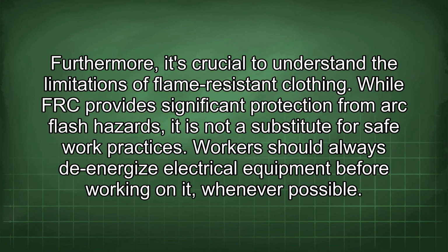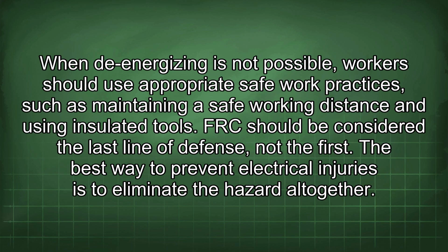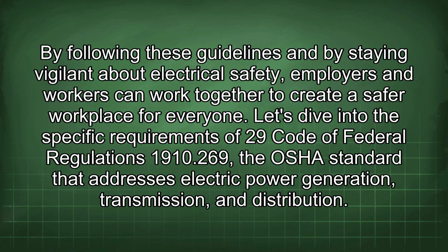Furthermore, it's crucial to understand the limitations of flame-resistant clothing. While FRC provides significant protection from arc flash hazards, it is not a substitute for safe work practices. Workers should always de-energize electrical equipment before working on it, whenever possible. When de-energizing is not possible, workers should use appropriate safe work practices such as maintaining a safe working distance and using insulated tools. FRC should be considered the last line of defense, not the first. The best way to prevent electrical injuries is to eliminate the hazard altogether.